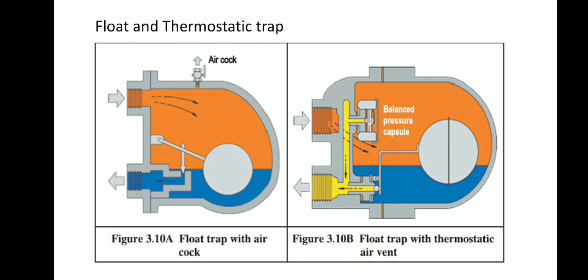Okay, then the efficient steam utilization and energy saving opportunities. The first one is monitoring of steam traps. For testing a steam trap, there should be an isolating valve provided downstream of the trap, and the test valve shall be provided in the trap discharge. When the test valve is opened, the following points have to be observed. First one is condensate discharge. Inverted bucket and thermodynamic disc type traps should have intermittent condensate discharge. Float and thermostatic traps should have continuous condensate discharge. Thermostatic traps can have either continuous or intermittent discharge depending upon the load. If the inverted bucket traps are used for an extremely small load, it will have a continuous condensate discharge.